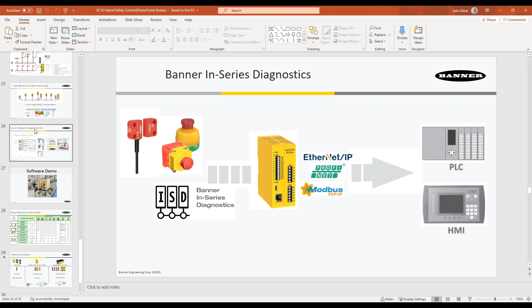The way you set this up is on the M plug—this device has safety inputs, so you tie 24 volts to the OSSD inputs of the first device. That's all that termination plug is doing, and then you connect your zeros together.